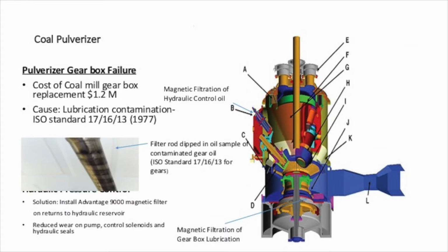Each 400 megawatt unit at Sundance has 5 of these coal mills. The smaller units have 6. They're a Raymond Bowl design. You have 3 journals, rollers that crush the coal. Each one of the larger mills will crush about 40 ton an hour.